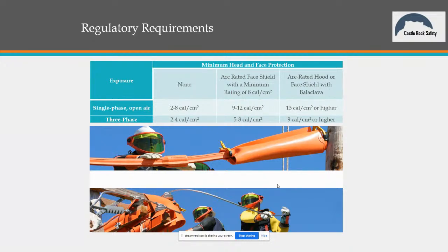That's interesting, didn't know that. And then for sure, if it gets up above 12, you've got to put the hood or a face shield with a balaclava on. Now, another thing about the face shield: 1910-269 allows you to exceed the rating of the face shield by 4 calories. So if I've got a face shield rated for 12 calories, I can wear that if the exposure is no greater than 16. They give us a little bit of slack since these face shields are only rated for 12 calories, but they allow us to wear it up to 16.